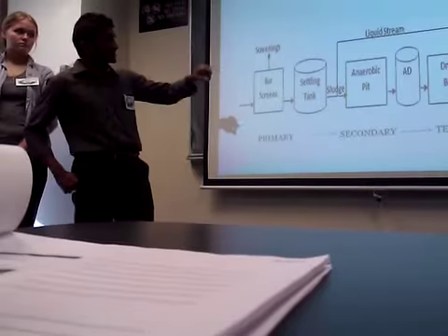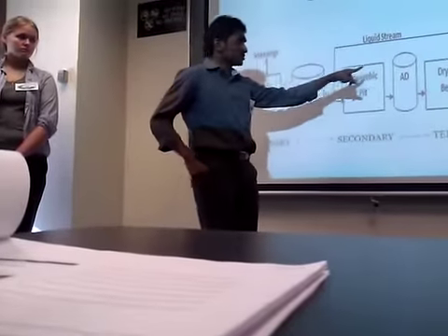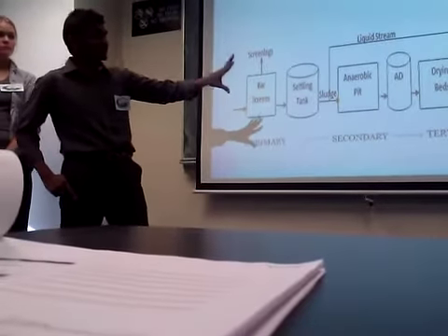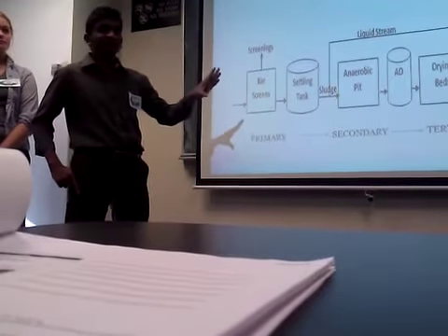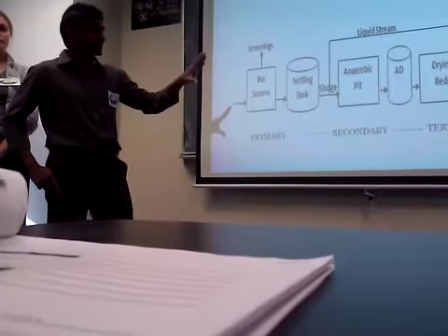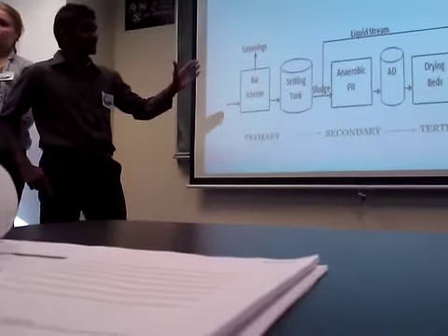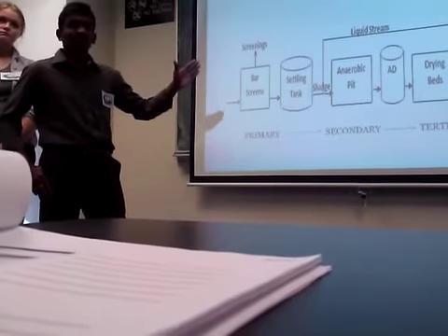Particularly in this area, the anaerobic zone, anaerobic region, it's ineffective. That's the reason why the effluent from the trickling filter is having high BOD, which is 65 mg per liter, and coliforms at 15,000 per 100 ml, which is a little bit more than the local recommendations.